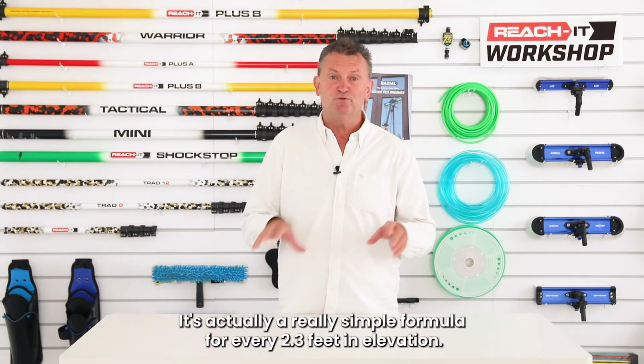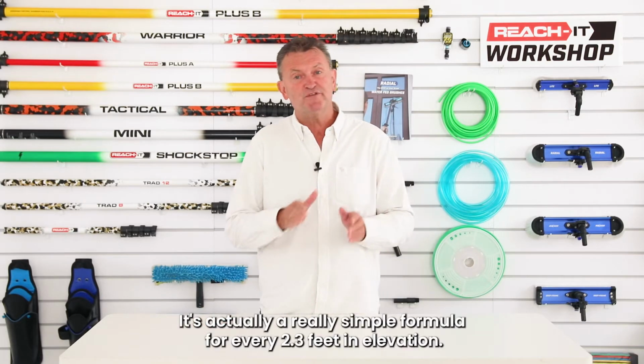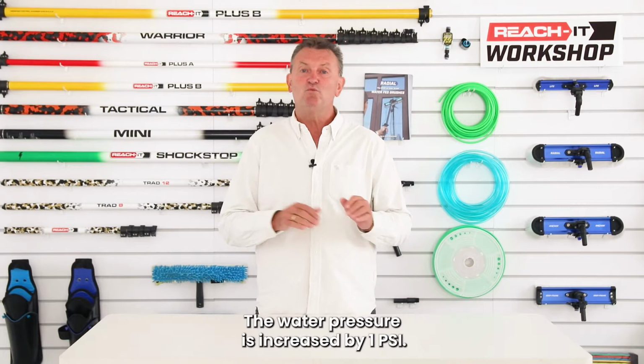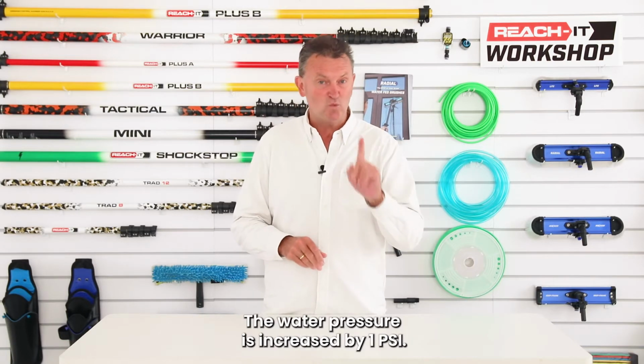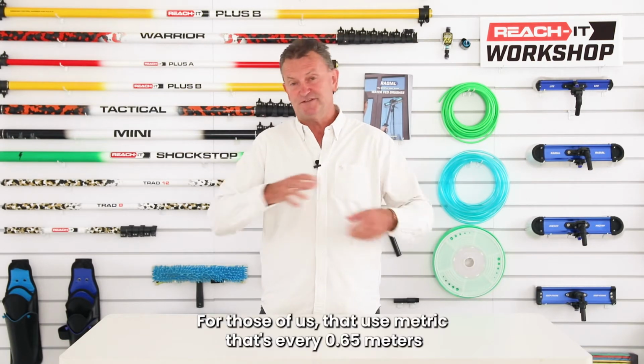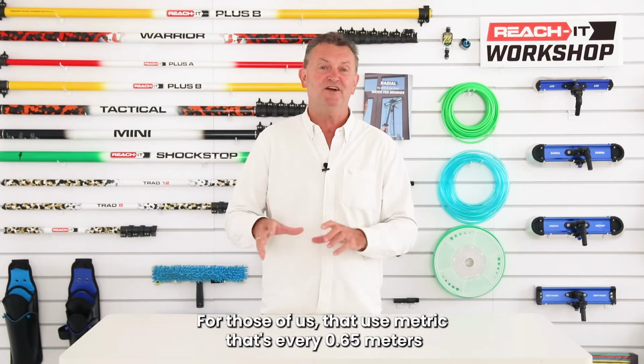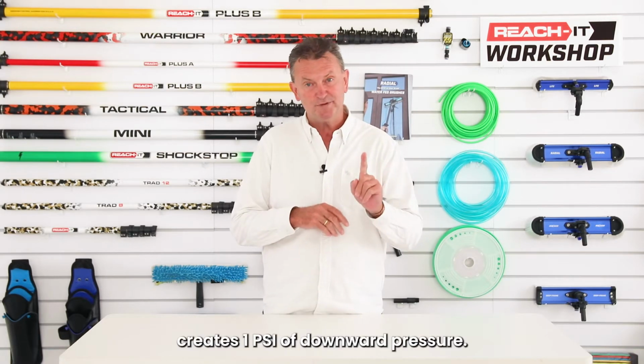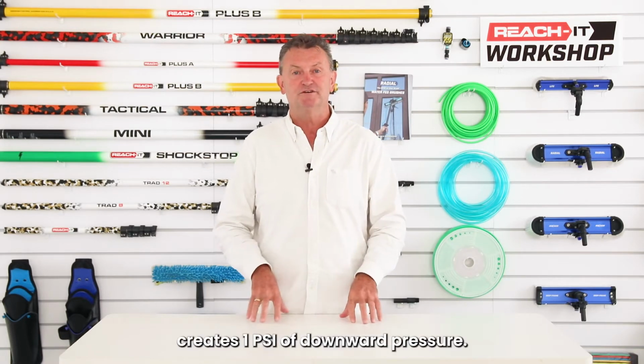It's actually a really simple formula. For every 2.3 feet in elevation, the water pressure is increased by 1 psi. For those of us that use metric, that's every 0.65 meters, creates 1 psi of downward pressure.